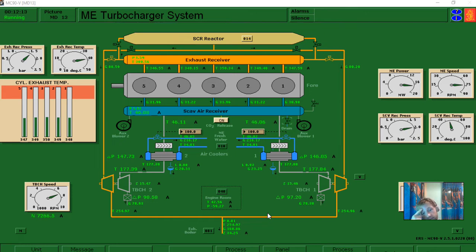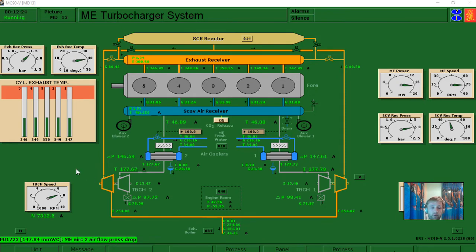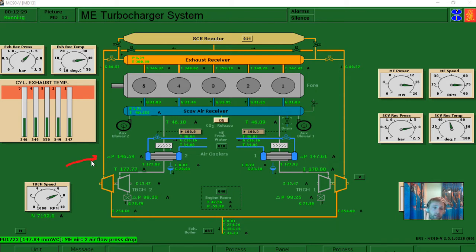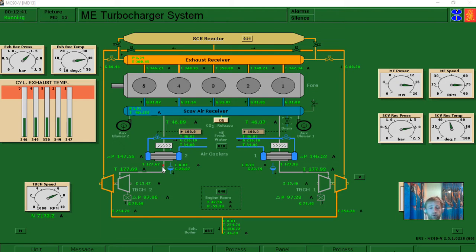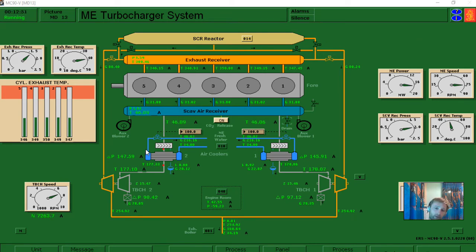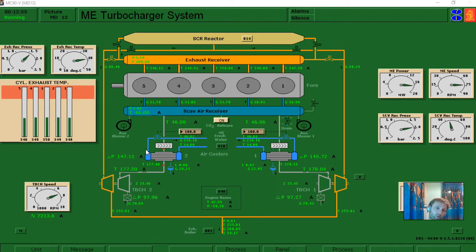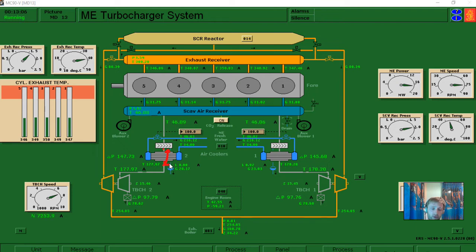Another thing that we can see here is the differential pressure of our air cooler, and what we mean here with DP or in Greek we say delta P. This is differential pressure across the entrance of the air from the turbocharger. This is the point which the air inserts and there is an outlet point where the air exits and is already cooled down. So the density of the air is much much higher than when it entered, and through this travel of the air we have a reduction of differential pressure.